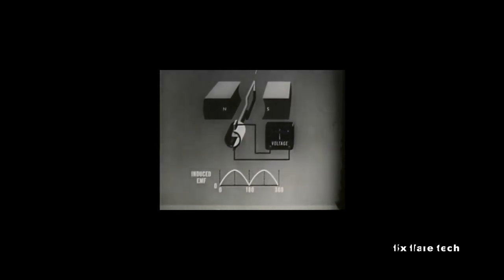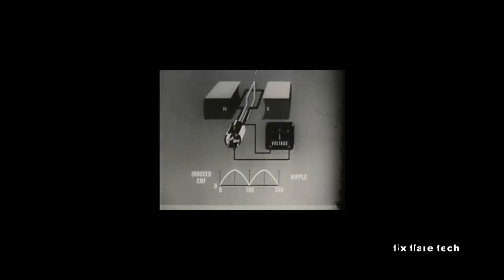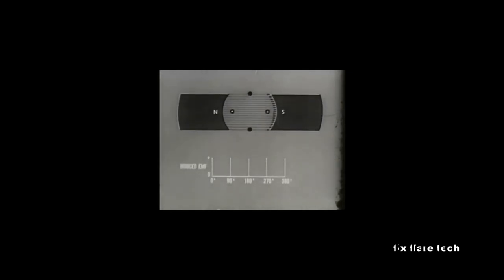The pulsation from zero to maximum, twice for each revolution of the loop, is called ripple. This ripple can be reduced by adding more loops and more commutator segments to the existing armature. Two loops at right angles connected to four commutator segments provide two outputs instead of one. These outputs are 90 degrees displaced, which combine to smooth the DC output.